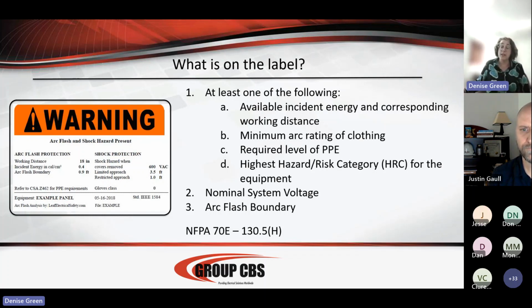I've been in facilities, I saw a facility and I felt really bad. Every single label in the entire plant was identical. Well, I can tell you right now that that's worthless. If every single label at every single amperage level of every breaker is identical, someone didn't do their job. And you can't trust those labels.